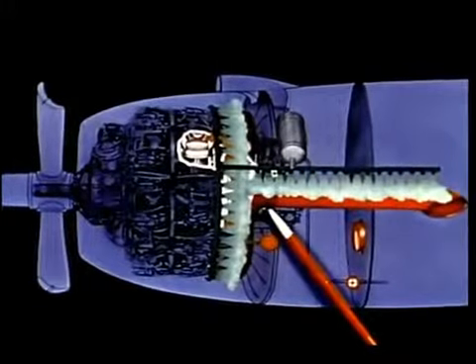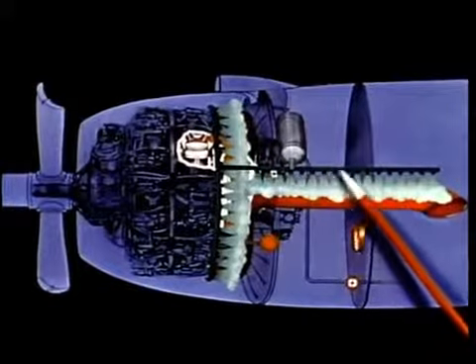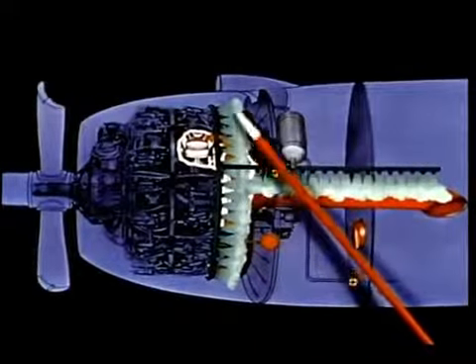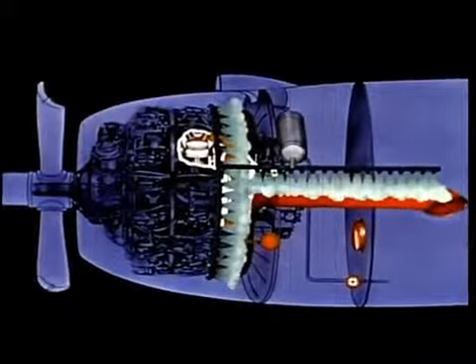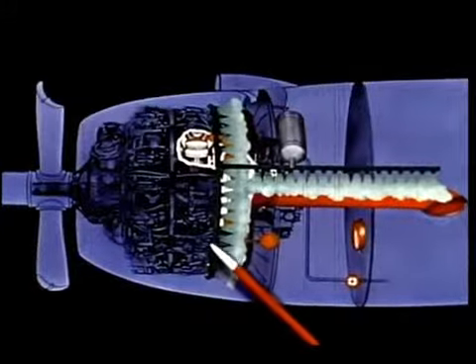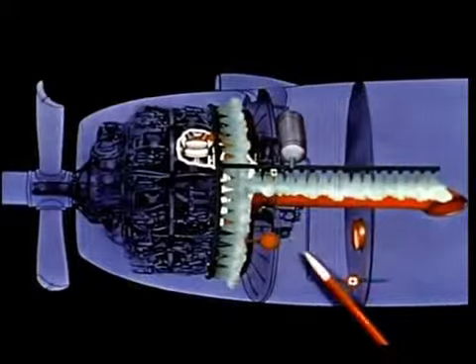In order to prevent ignition on the hot metal of the exhaust system, a water spray is used to cool all of the exposed metal, which is hot enough to ignite the combustibles. In the few seconds needed to cool the metal to safe temperatures, an inert atmosphere of steam generated by the water evaporating from the metal itself shrouds this potential ignition source to render it impotent. The portion of the water spray system which services the exhaust collector ring is this 3/4-inch diameter tubing, bent to conform approximately to the shape of the collector ring. The exhaust system receives water over its entire surface from its spray nozzles.